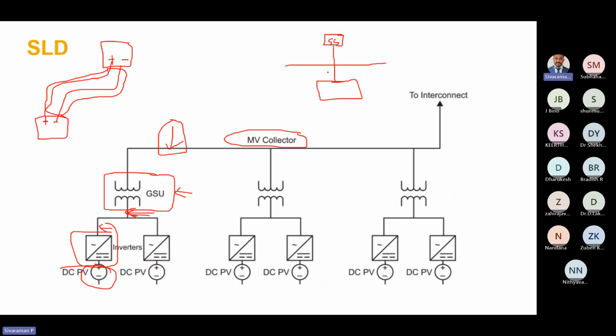For an example, suppose this is a point, POI, point of interconnection, where we have to connect this PV plant. After this line, this will be the plant side. This will be a transmission line from the PV plant to the interconnection substation. This portion will be the substation, the TNEB substation. Are we going to comply with this 50 megawatt, 3500 megawatt hour at the plant level location, or at the interconnection substation location?